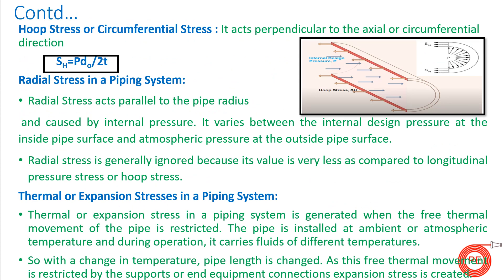Hoop stress, also known as circumferential stress, is another important stress acting along the body. Unlike longitudinal stress, which acts parallel to the piping axis, hoop stress acts perpendicular to the axial direction — in the circumferential direction. It is given by: S_H = P·D₀ / (2t), where P is internal pressure, D₀ is the outside diameter, and t is the pipe thickness. This stress also tries to deform the piping system.